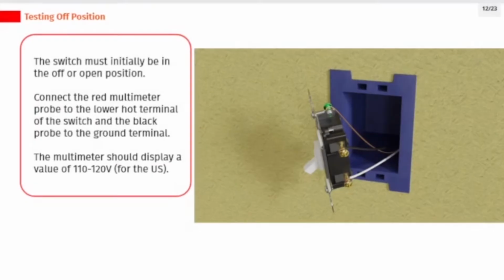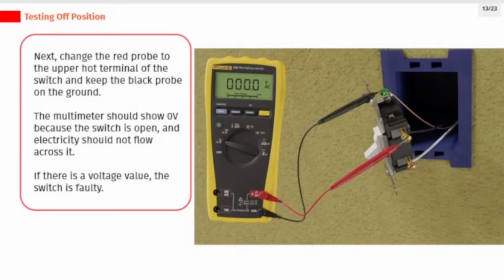The switch must initially be in the off or open position. Connect the red multimeter probe to the lower hot terminal of the switch and the black probe to the ground terminal. The multimeter should display a value of 110 to 120 volts for the US. Next, change the red probe to the upper hot terminal of the switch and keep the black probe on the ground. The multimeter should show 0 volts because the switch is open, and electricity should not flow across it. If there is a voltage value, the switch is faulty.